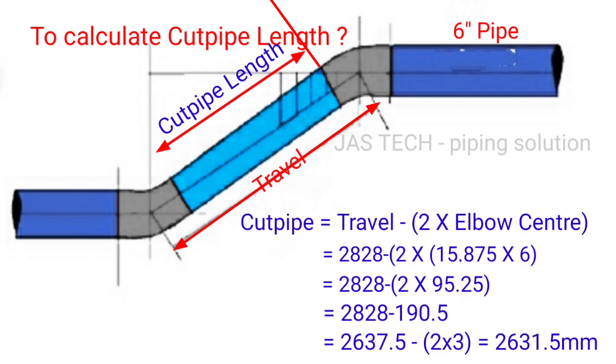So 2828 minus 190.5 mm equals 2637.5 mm, minus 2 root gap, 2 times 3 mm. So the final answer is 2631.5 mm. That is the cut pipe length.